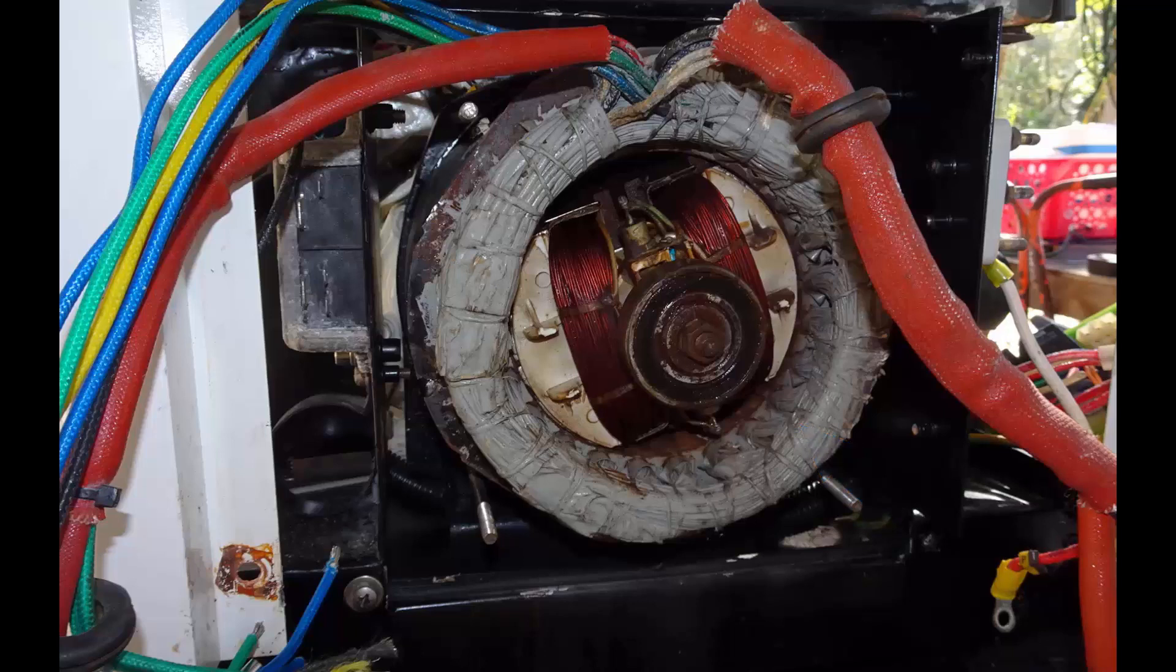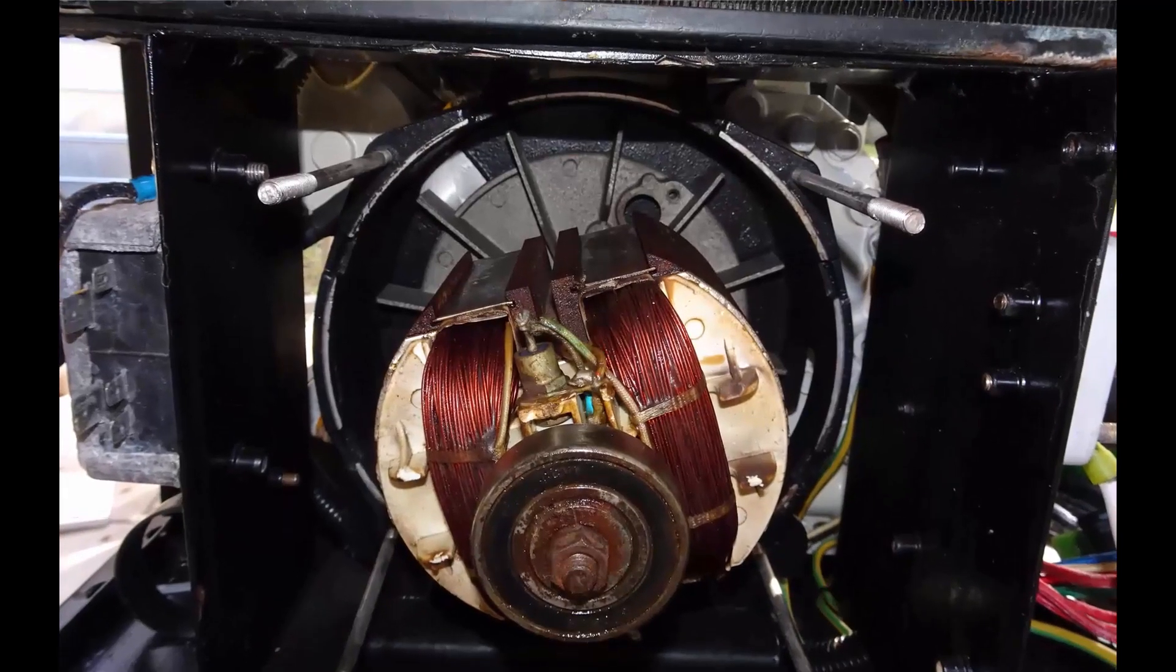And that causes current to flow in this rotor armature. The current flow in this rotor armature causes more induced voltage into the exciter windings. They cause more induced current into the rotor armature, and it snowballs into saturation.